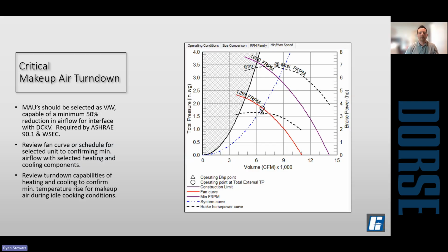One thing that's critical when you're doing demand control: in some cases, maybe the kitchen consultant specifies the hoods. The engineer's responsible for selecting the mechanical equipment to go along with that. It's important that you get a makeup air unit that's configured for variable air volume and that's capable of a 50% reduction in airflow. It's not an easy thing to do. And so you should always check with the manufacturer you're working with to get the minimum airflow and make sure the makeup air is going to work with the hood controls.